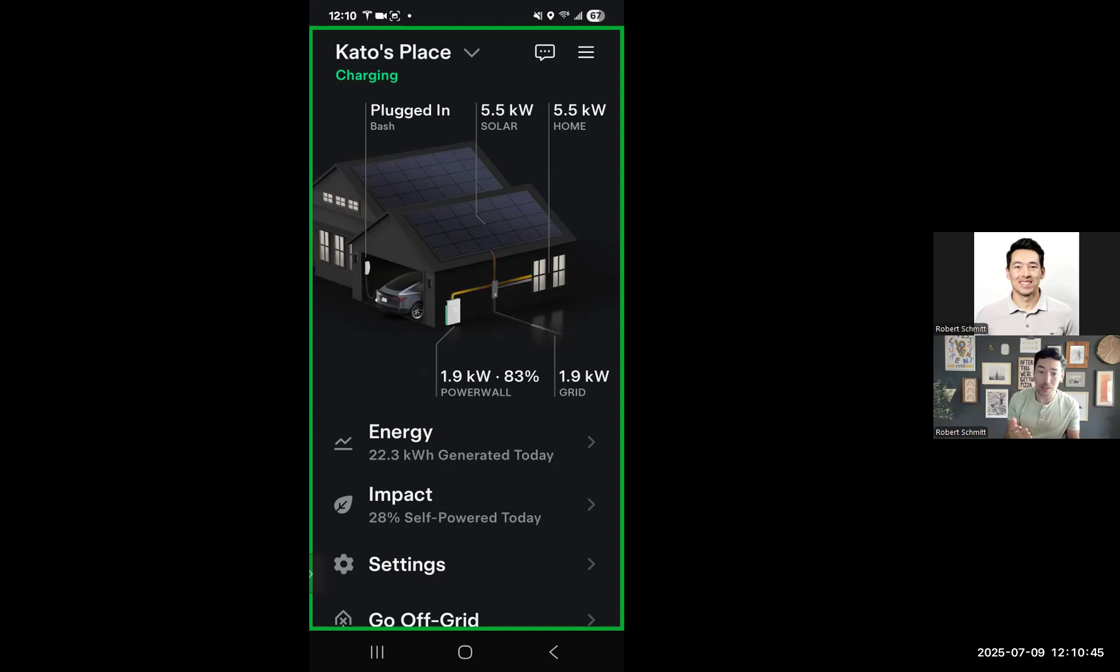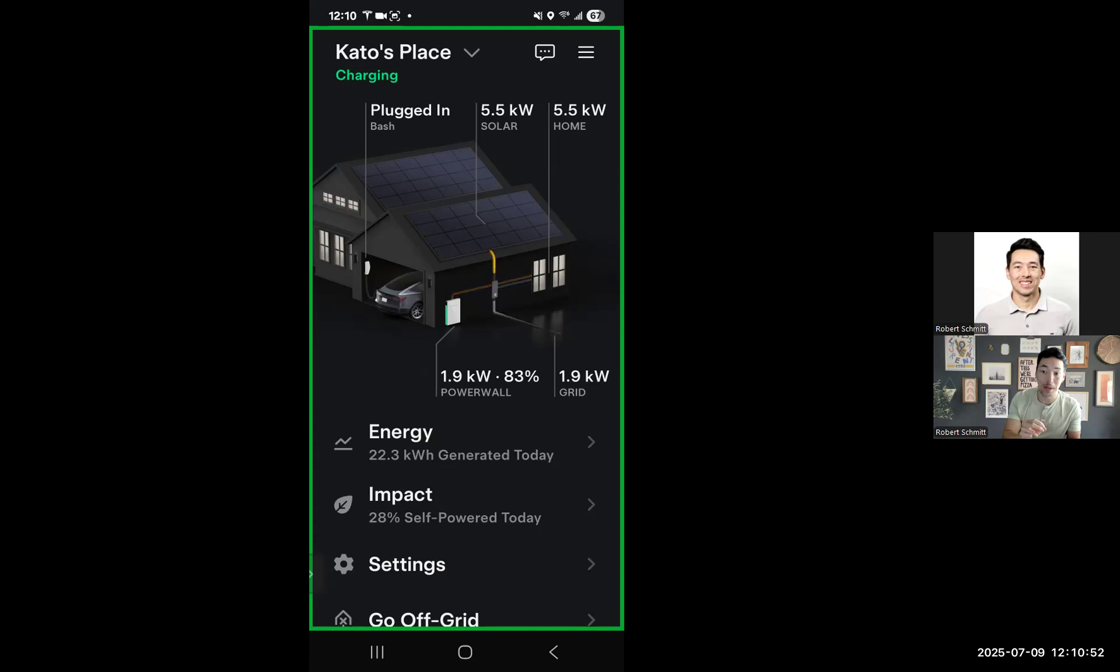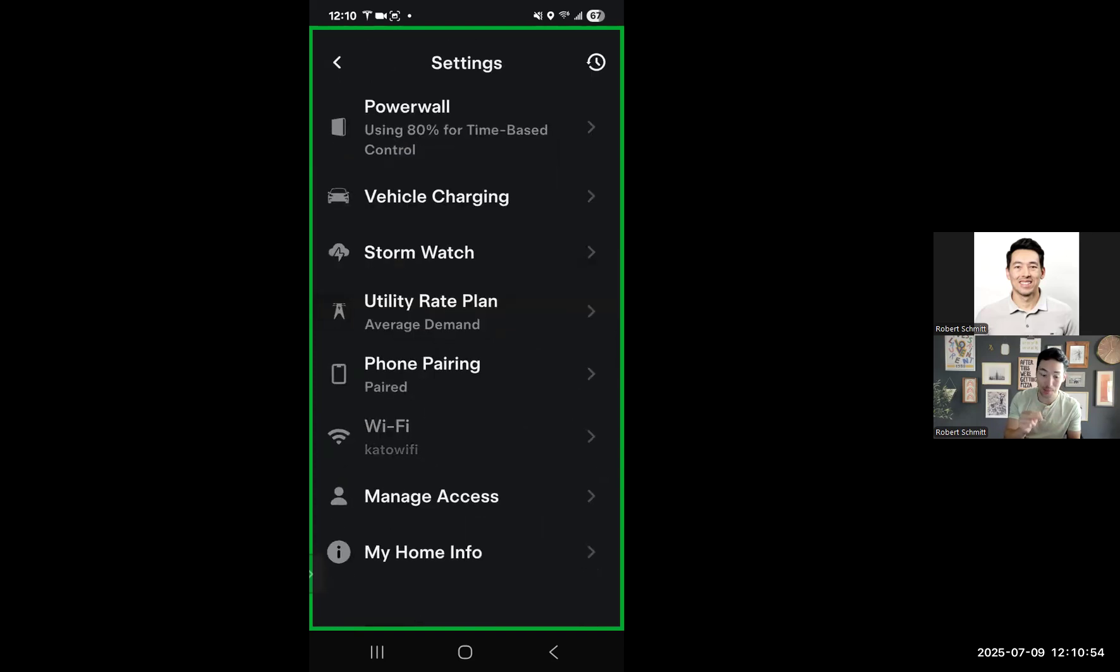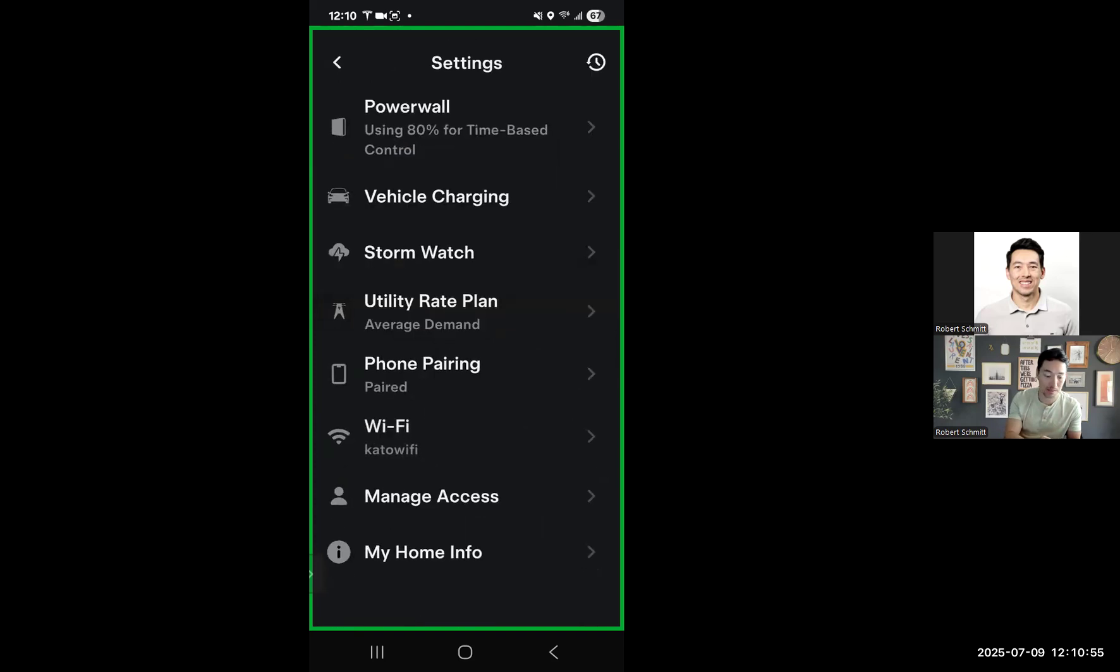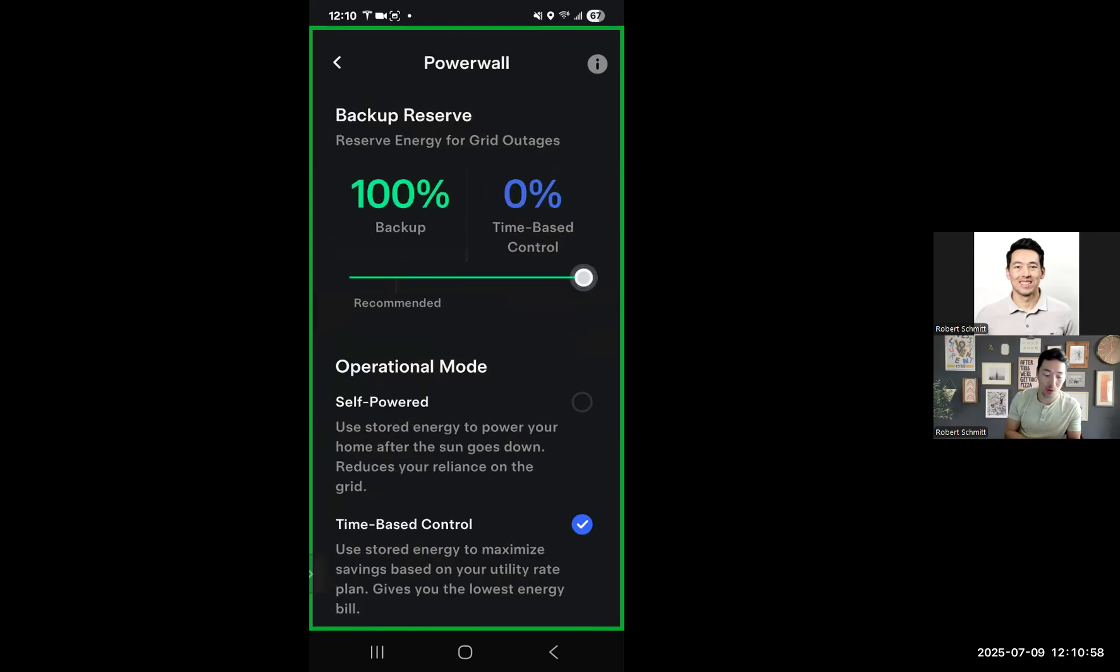And so to fix this is to basically go into settings. And this is a two-level fix. One is a very annoying way to basically babysit this thing every day until the permanent fix is in place, which is going into your settings, going to time-based control, and bringing that to 100% backup.